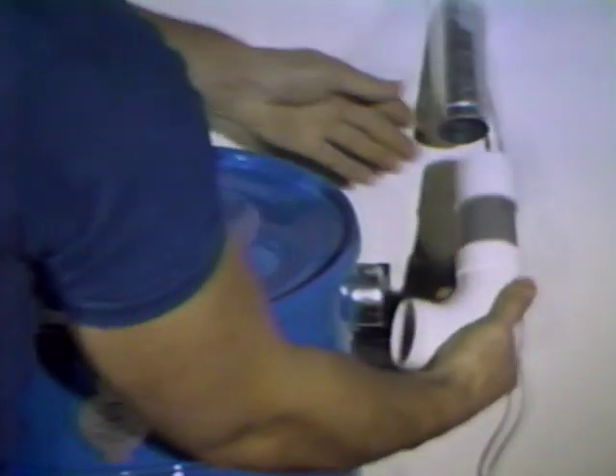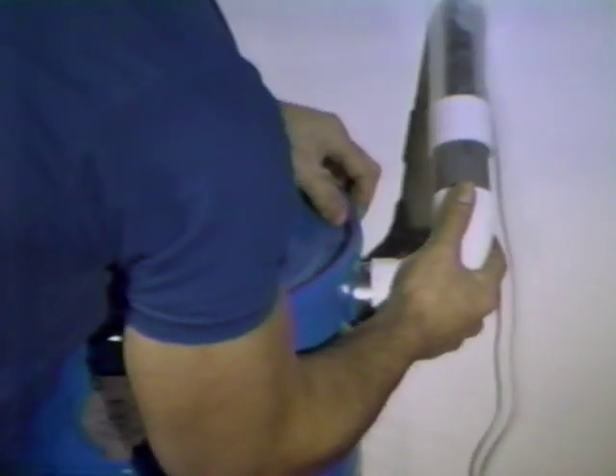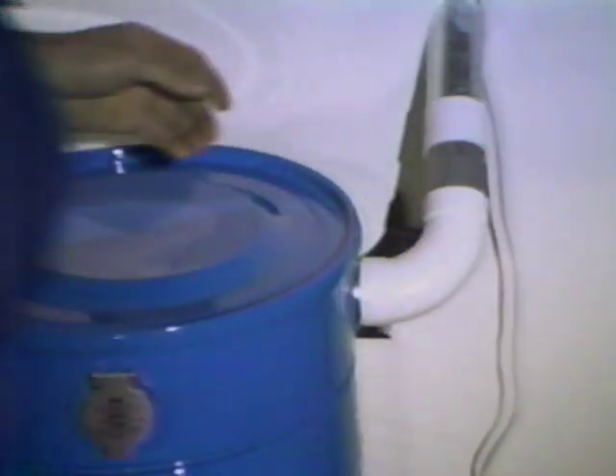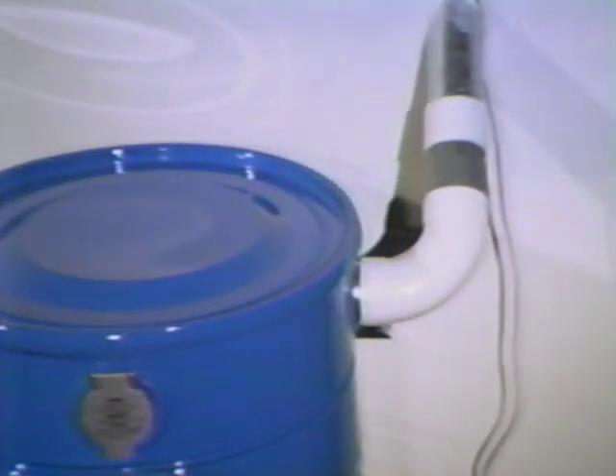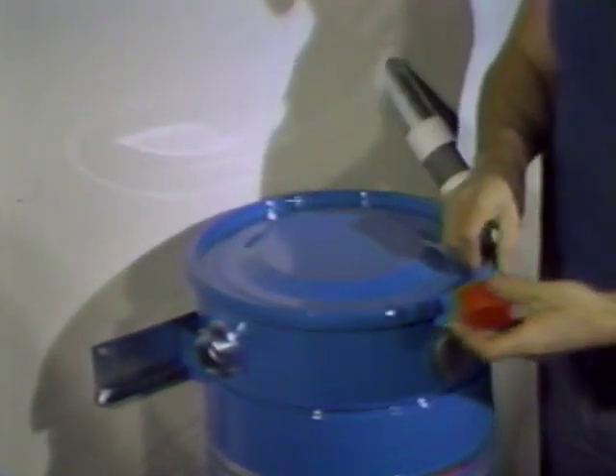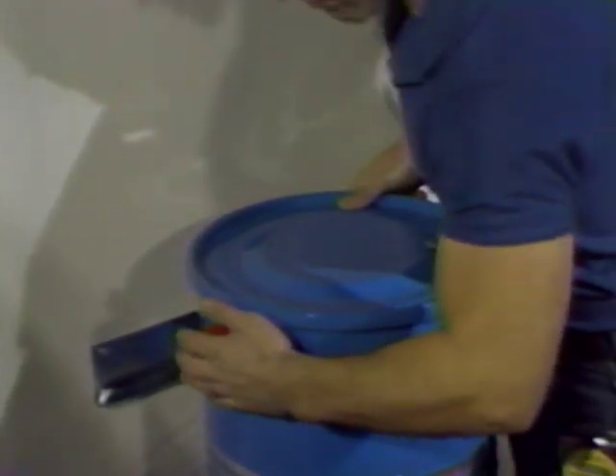Using a Sweep 90L, a short piece of pipe, and a coupling, connect the power unit to the steel tubing. Inside the unit, you will find a red pipe cap. Use it to seal the unused intake neck. Route the low voltage lead to the lower right-hand side of the power unit. You will see 2 pairs of wires connected by wire nuts. Remove one wire nut and connect one of the low voltage leads. Connect the other low voltage lead to the other pair of wires.